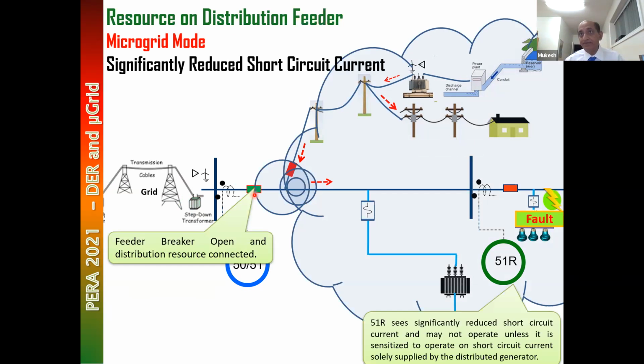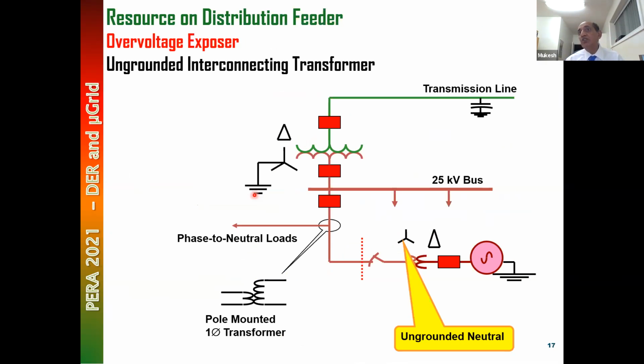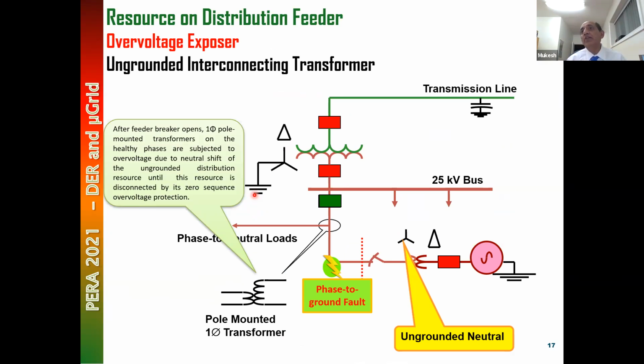I want to make sure all of you are with me, because this is a very important point. The ground fault current comes from here, and this circuit breaker opens. Now with this circuit breaker open, no current is coming, so this protection will never operate because no ground fault current is coming. This is a line to ground fault, and this source is still connected. We are subjected to √3 higher voltage because of neutral shift. There is no neutral, so the neutral will shift to the faulted phase. Now the phases are subjected to line voltage. This transformer is now subjected to √3 higher voltage. It will get severely saturated, high eddy current will flow, and it will damage this transformer. So if you leave it ungrounded, that's what is going to happen.